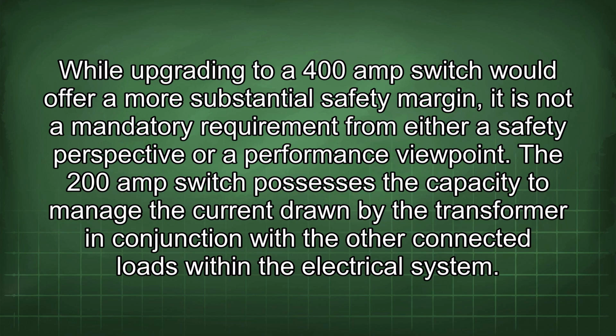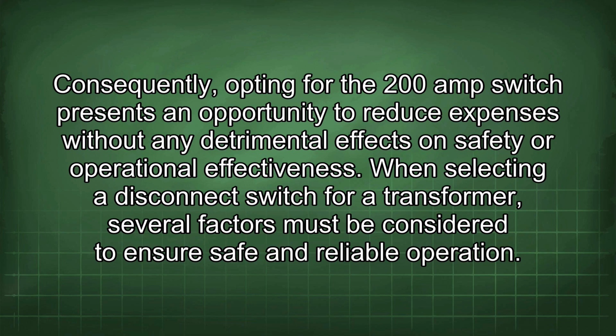The 200 amp switch possesses the capacity to manage the current drawn by the transformer in conjunction with the other connected loads within the electrical system. Consequently, opting for the 200 amp switch presents an opportunity to reduce expenses without any detrimental effects on safety or operational effectiveness.